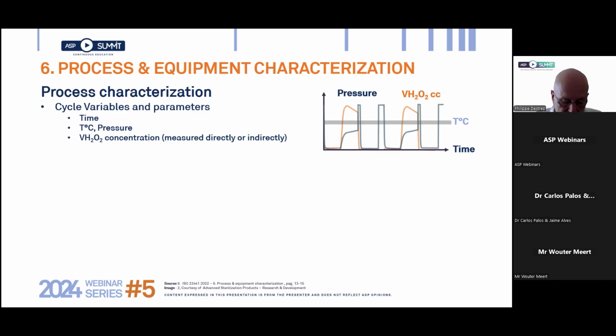Temperature and pressure are not as central as they are for other sterilization processes like steam, but H2O2 activity, like all chemical activities, is influenced by temperature, and vacuum is needed to ensure penetration of H2O2 in packages and devices. For H2O2, like for all chemical processes, the key determinant of efficacy is the concentration of the sterilizing agent. It can be measured directly by an H2O2 monitor. Can you click, Jamie? Or indirectly via dose and pressure control. Sterilizers do both, that is to say, direct measure of H2O2 monitoring and indirect control via pressure control and many other things. Can you click again?